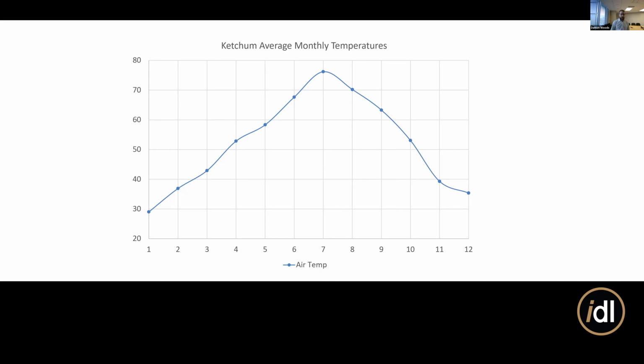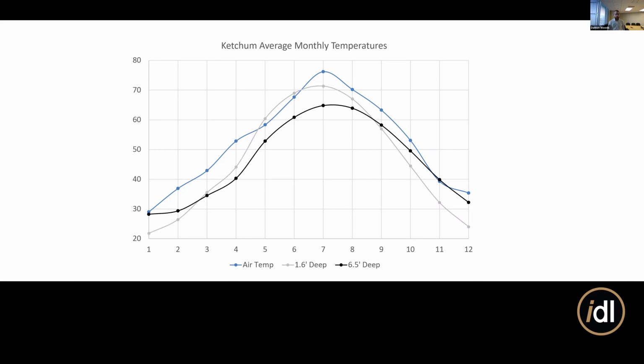If we look at the ground just 1.5 feet deep, it's even a little colder than the air temperature, but it gets a little less warm during the summer. As we drill further down, about 6.5 feet deep—about the minimum depth for a ground source loop—you can see significant mellowing of the trend, less extremes. These are average monthly temperatures, but we're also avoiding the daily extremes you'd see in air temperature popping up and down. Ground temperature moves much more slowly and evenly, keeping to a general profile closer to between 30 and 50 degrees.